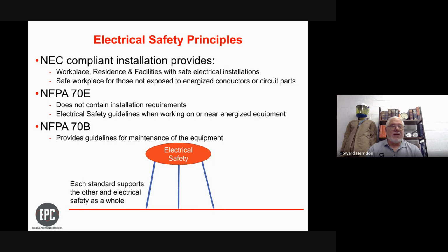NFPA 70E does not contain any installation requirements, but has to do with electrical safety guidelines when working on or near energized equipment. These could be simple guidelines of working on something energized, de-energizing a system, or as simple as resetting a tripped circuit breaker.